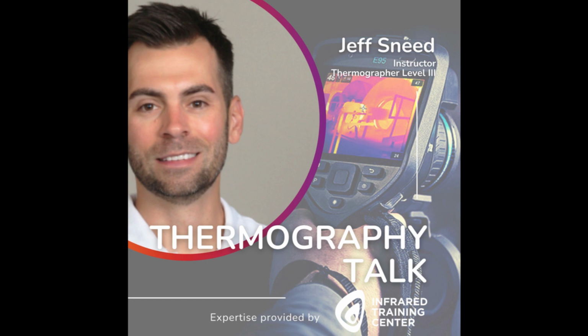Next up is the limited approach boundary, 42 inches in this case. This talks about qualified versus unqualified workers. If you go back to the last webinar that we recorded, John Wagner, one of our senior instructors, goes into the newer edition changes for 2024 NFPA, and he also goes into the differences between qualified and unqualified workers, because that is part of NFPA's classification on who can and cannot be working on electrical equipment. The limited approach boundary talks about if you're not a qualified worker, you should never enter that boundary. So you never should get closer than that if you're not a qualified worker. Only qualified workers can get within that boundary and work on the equipment safely.